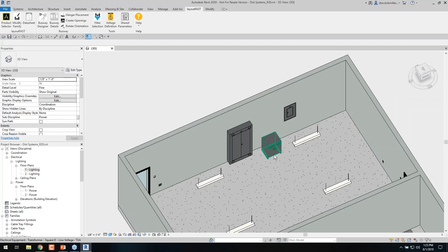So the first thing to doing this for circuiting is to establish your distribution systems. If you go to your MEP settings, your electrical settings, we see that we have certain voltages defined. That just basically says that we have a voltage called 480, and what it means is that it's 480 volts, but it has a range of 460 to 490. So you can define any voltages you need.